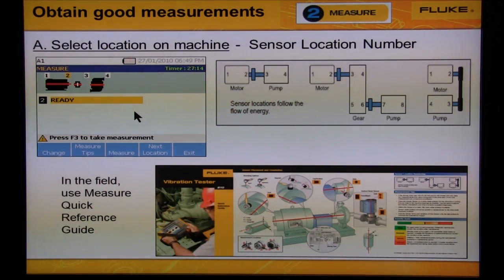The 810 is designed to help you obtain good measurements. There are three screens that make this process easy. On the first screen, use the machine icon and select the bearing location the sensor is on. The current bearing location shown is for bearing number two, which is on the motor. To start the measurement, press Measure. To go to the next location, press Next Location. The image on the right shows how sensor location numbering follows the flow of energy down a machine.